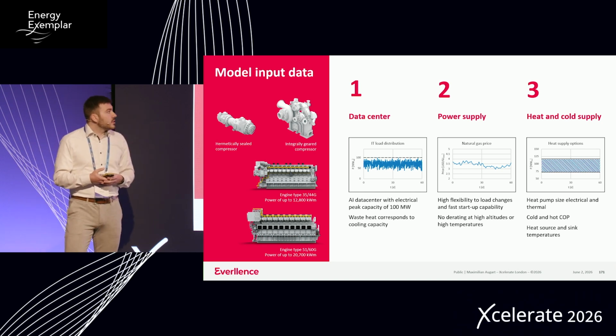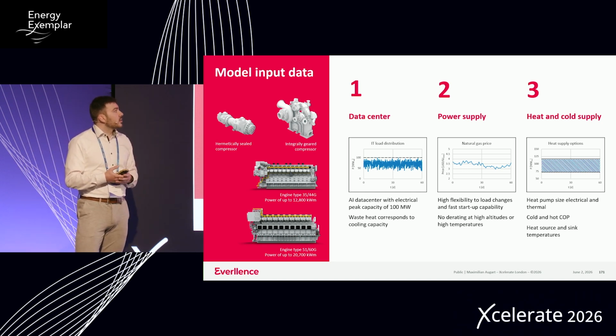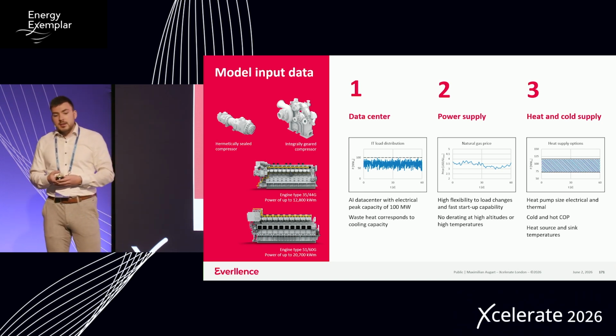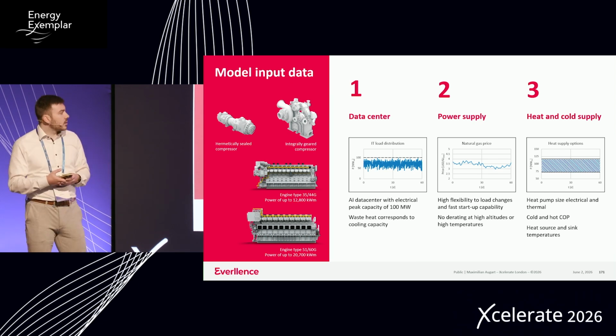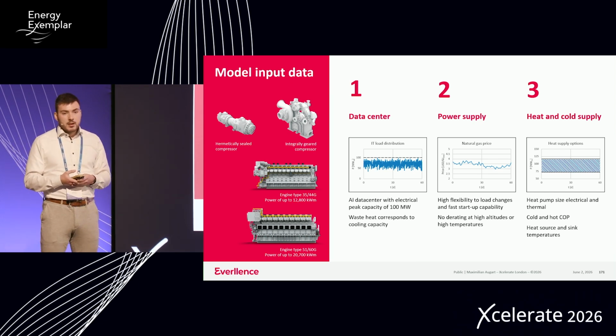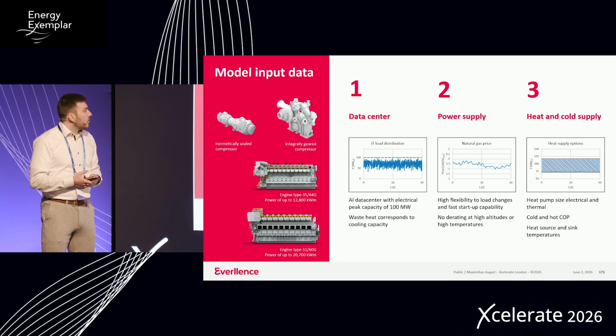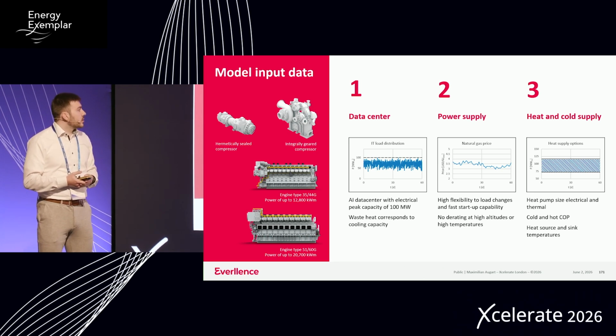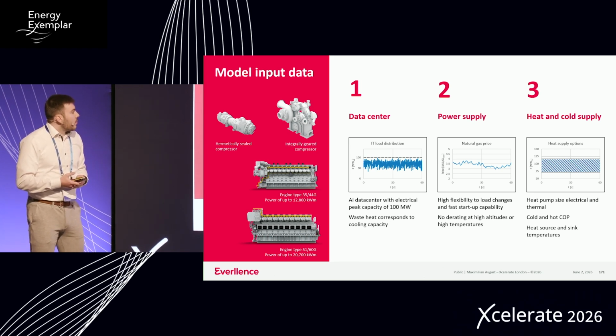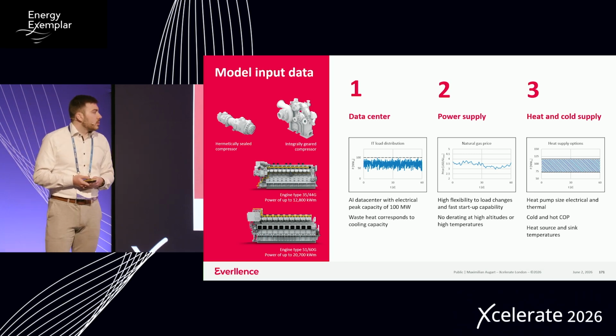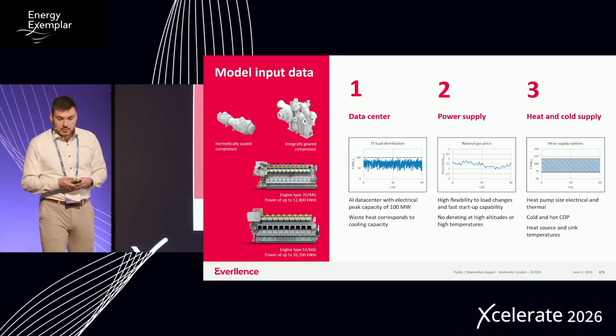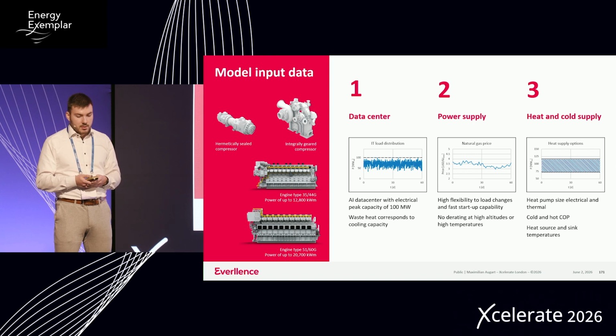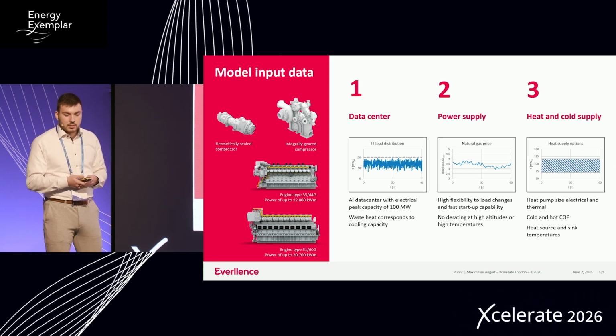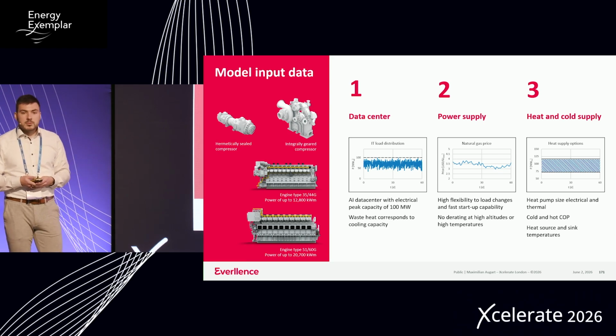The third thing is the heat and cold supply. I want to achieve a constant heat and cold supply for the district heat energy system, which is why we use a heat storage between the heat pump and the district heat system. It's also important to look at the cold and hot COP of the heat pump, so how efficiently it produces heat and cold.